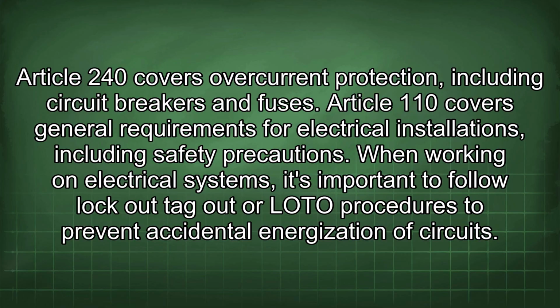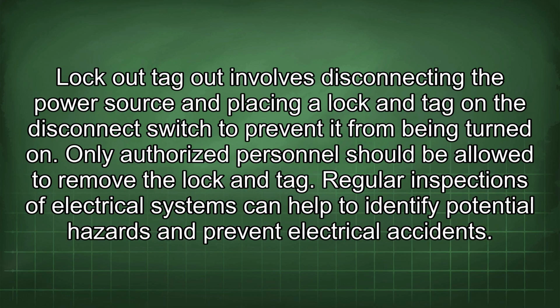When working on electrical systems, it's important to follow lockout-tagout, or LOTO, procedures to prevent accidental energization of circuits. Lockout-tagout involves disconnecting the power source and placing a lock and tag on the disconnect switch to prevent it from being turned on. Only authorized personnel should be allowed to remove the lock and tag.